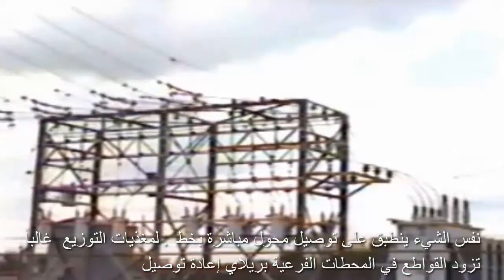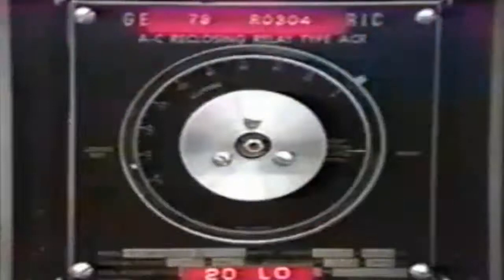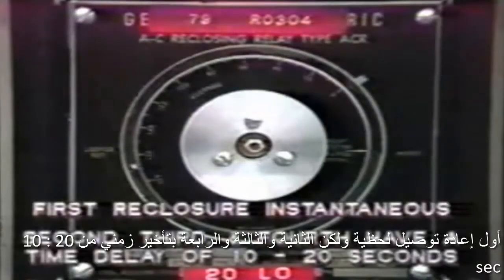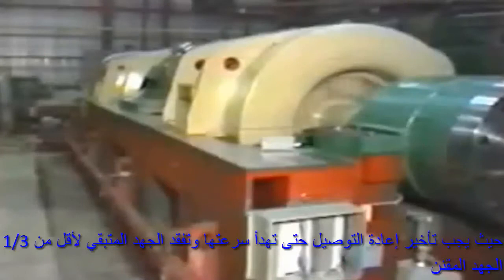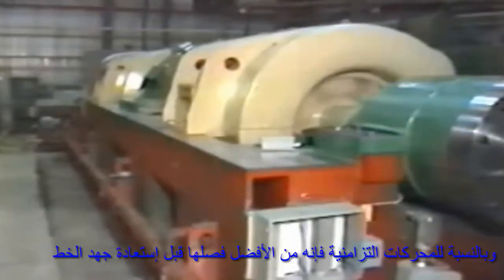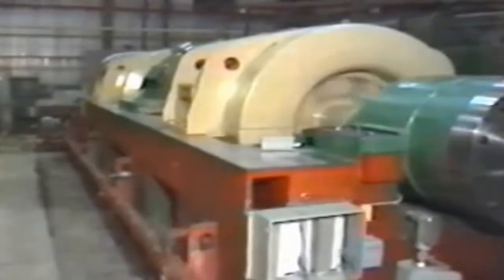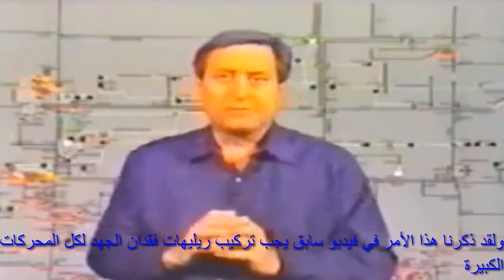For distribution feeders, the breaker in the substation is often fitted with a reclosing relay. The first reclosure may be instantaneous, but the second, third, and fourth will each have a time delay of 10 to 20 seconds. In setting the reclosing relay, it's necessary to know the types of load which are supplied by the particular feeder. For example, the feeder may supply an industrial load which includes large induction motors. Reclosure must be delayed until the motors have time to run down and reduce their residual voltage to less than 1/3 of rated. With synchronous motors, it's preferable to trip the motor before restoring the voltage to the line. You'll remember we discussed this matter in an earlier tape. Loss of voltage relays should be installed on all large motors.